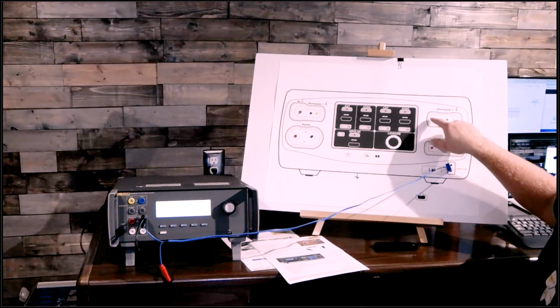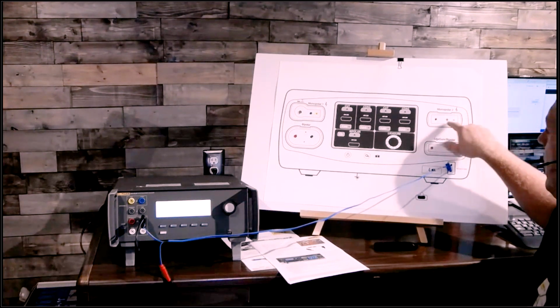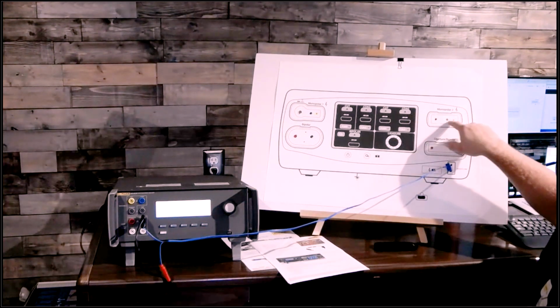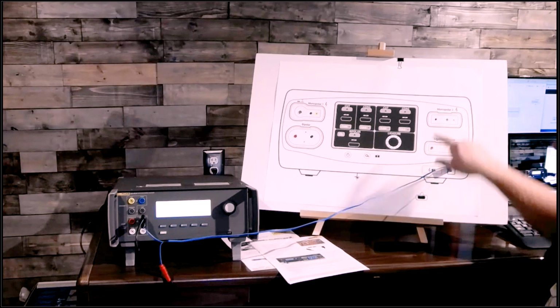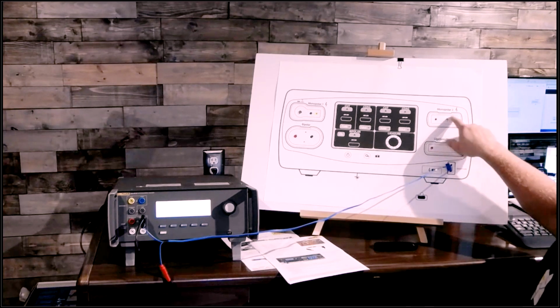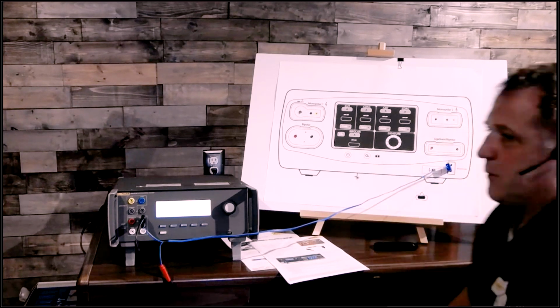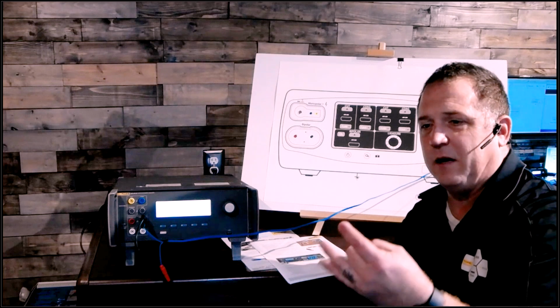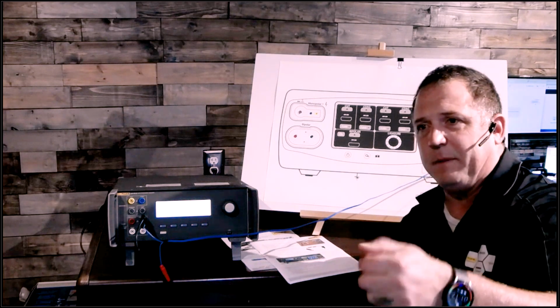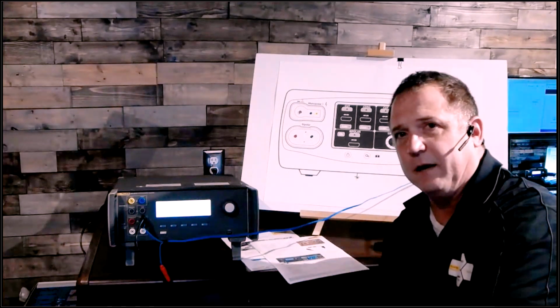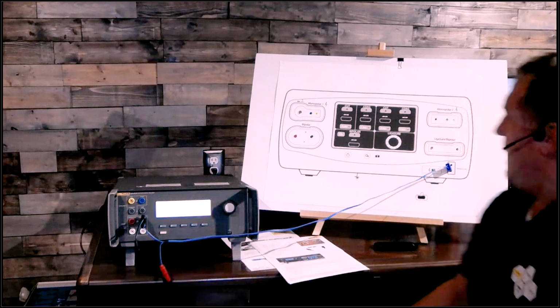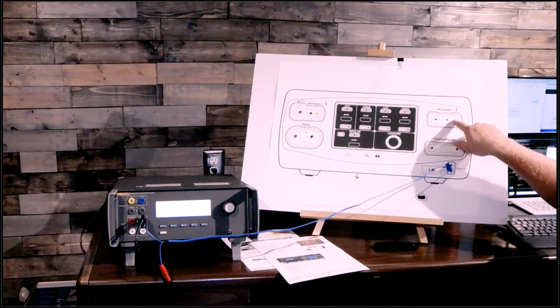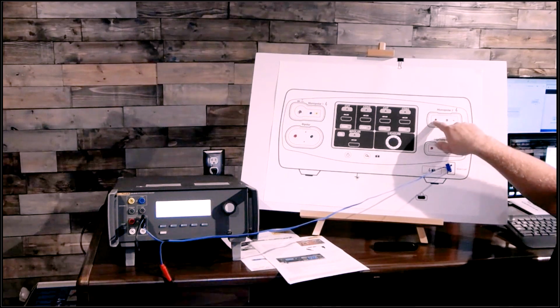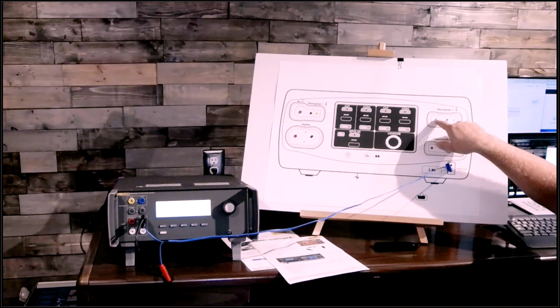So now I'm just going to pretend we're going to test monopolar 2. If you look at these ports for monopolar, you're going to notice there are 3 similar sized holes in it, 1 by itself and 2 that are together. If you look at your handpiece, you'll notice there are usually 2 buttons, a yellow and a blue. One's for cut and one's for coag. When you push the yellow button, it jumpers the yellow button to the red, and it activates the energy output. The one that's by itself is usually the energy output.